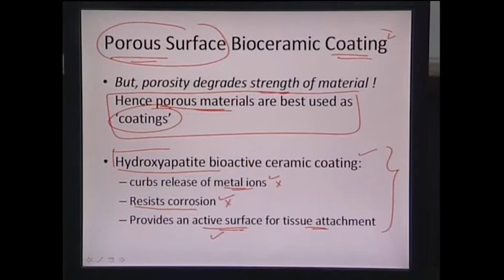So these are the important advantages of utilizing a bioceramic coating: it can take out all the negative effects of a porous material and just serve as a coating. That coating will limit the release of metal ions, because biometallic materials generally serve as implants, and it will restrict the release of metal ions into the body. It can provide a corrosion resistant coating onto the metallic implants. At the same time, it will serve as an active surface where tissues can attach themselves and grow comfortably on its surface.